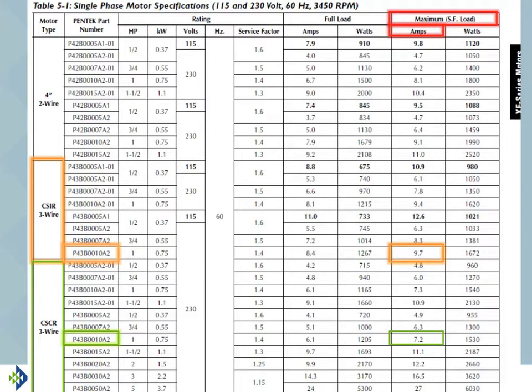So you can see there really is a difference. And if you look at the kilowatt difference, it's a little over 140. That's going to make a little difference too. The main thing I want you to understand here is amps are heat. So by reducing the heat, you extend the life of the motor. And that's why I always recommend, no matter what size motor you've got, to always use a cap start cap run control box. We do make cap start induction run control boxes simply because, yes, they do work and you've been taught for years that you can use them. So if you really want to, I can't stop you, but I'm strongly going to encourage you to always use cap start cap run control boxes. Okay?